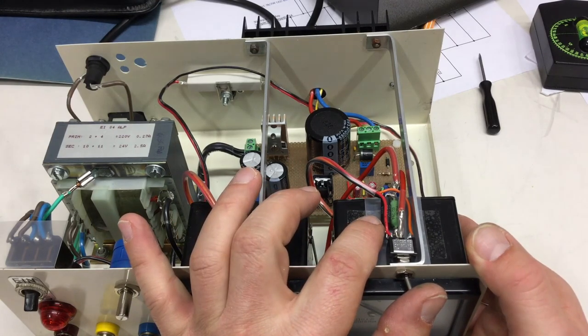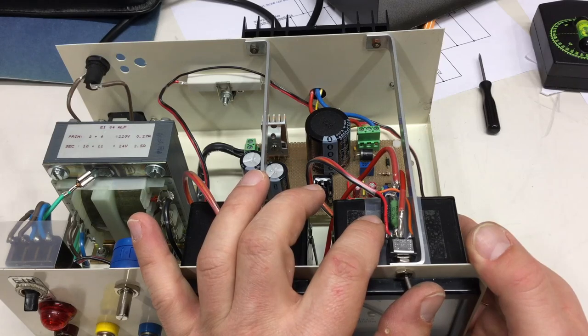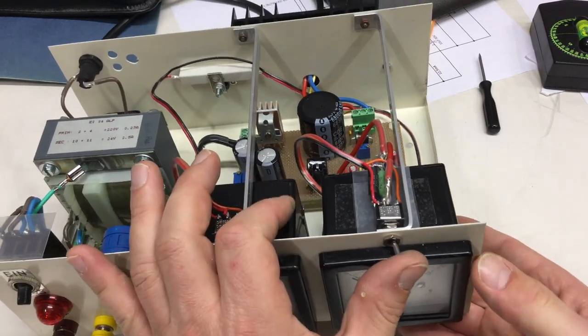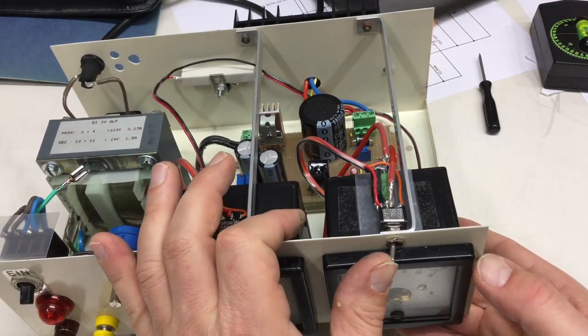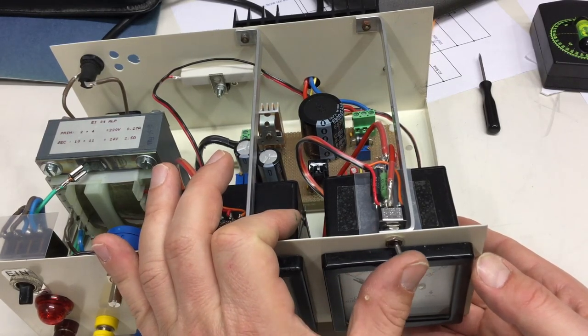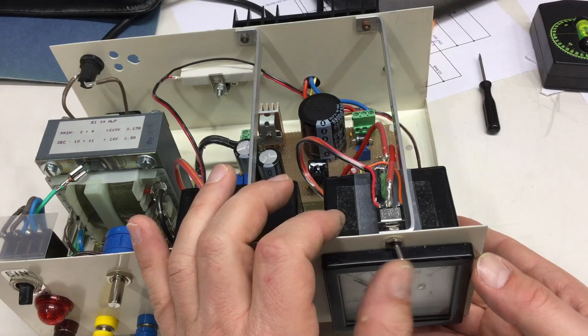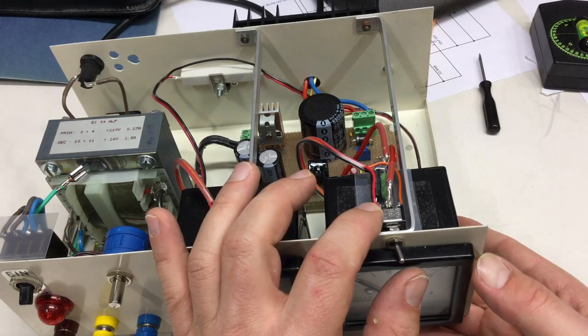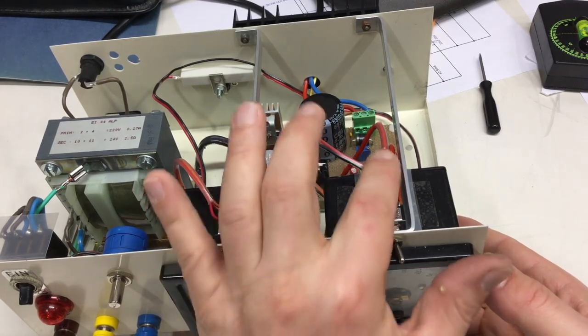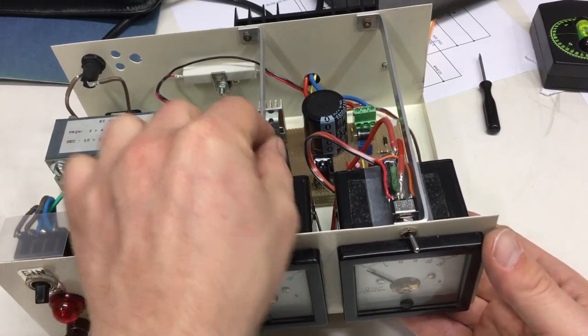Then a few dozen milliohms plus minus of the switch does nothing. I mean we're talking here, the instruments themselves are accuracy 1.5% on full scale. But with shunts here, with I think the smaller one is 0.07 ohms and the bigger one is 0.33 ohms, a few dozen milliohms difference on each switching cycle or when the switch ages, that's a huge difference.